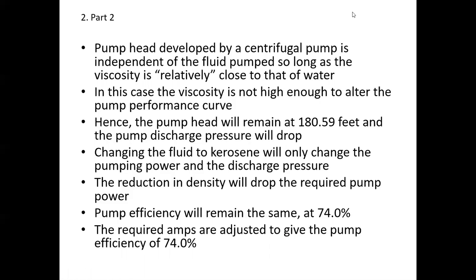Okay. So in this case, the viscosity increase is not enough to significantly alter the pump performance curve. That means the pump head will remain at 180.59 feet, and in order for that to occur, the discharge pressure has to drop, as we'll see when we go to the pump head calculator. So changing the fluid to kerosene will only change the pumping power and the discharge pressure.